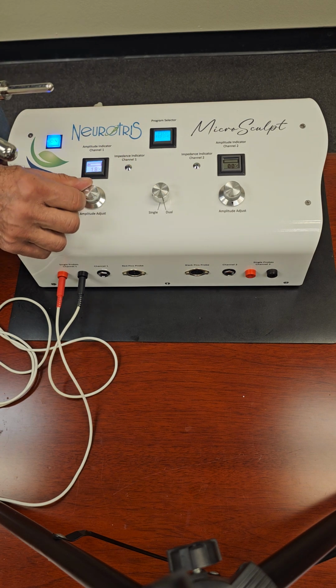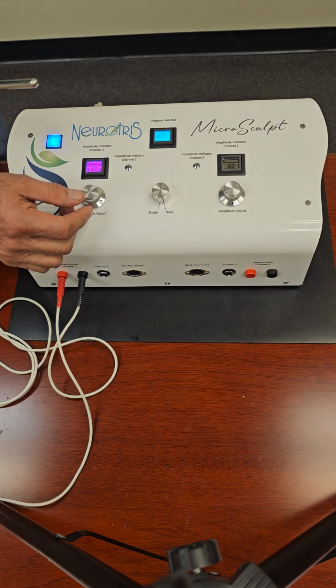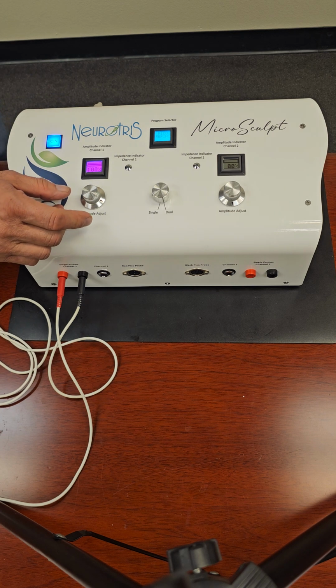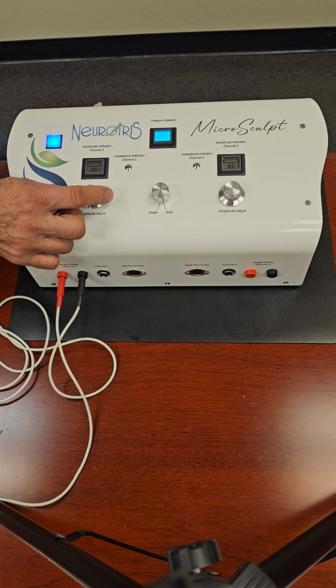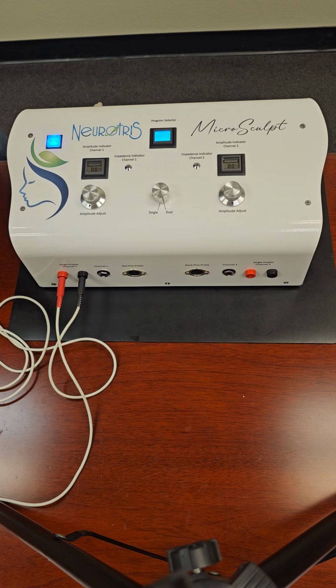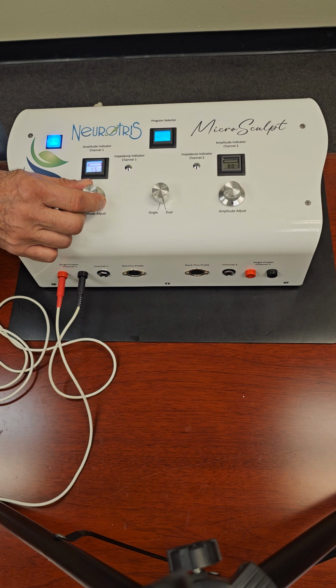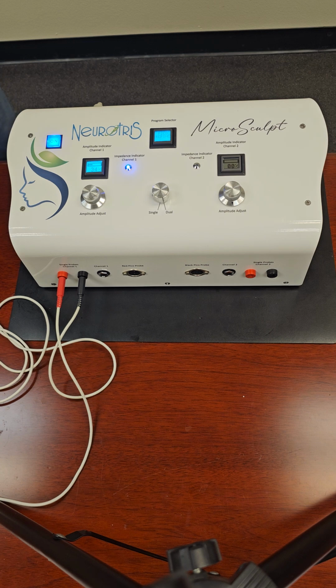So right now I have it at 0. I can go to 100. They don't come on because I don't have it on the skin. So once I put it on the skin, I'm going to turn it up until the lights come on. That means that's going to be the proper level. So I'm turning it on here, here, here. So for me, it works at about 36. So that's my level. That's my optimal level to be when I'm doing a treatment, because that shows that my skin impedance is going to be getting the most amount of current delivery when that light comes on.